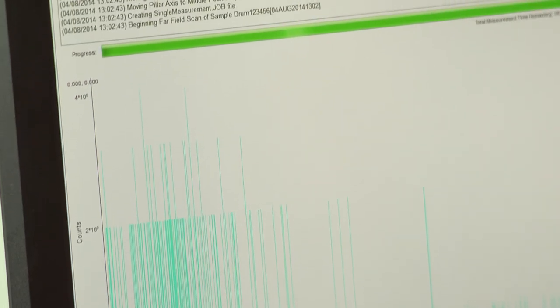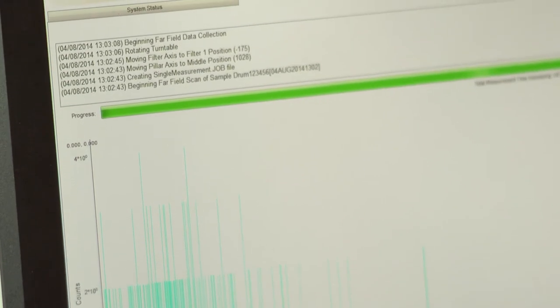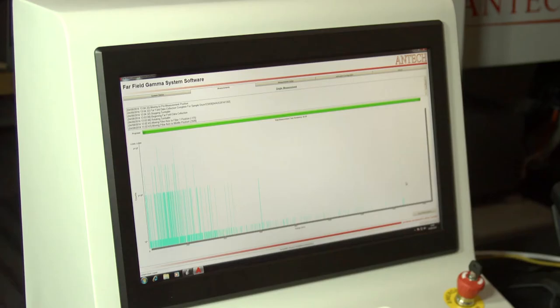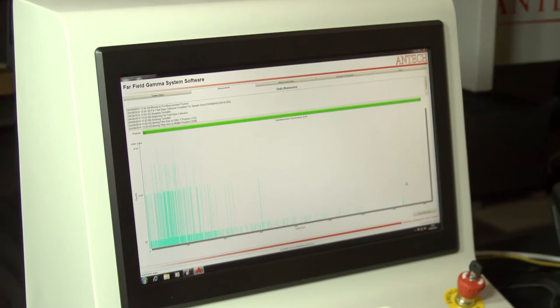For drums with intermediate density and a higher degree of matrix heterogeneity, more accurate measurements can often be obtained using the segmented gamma scanner method.